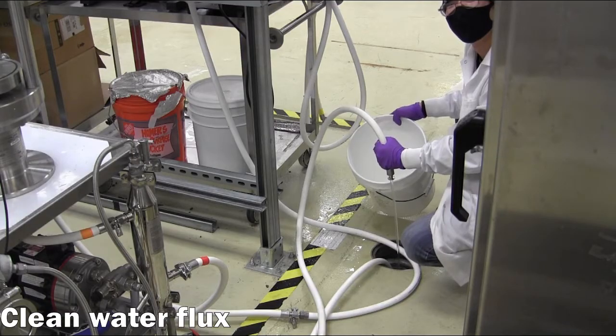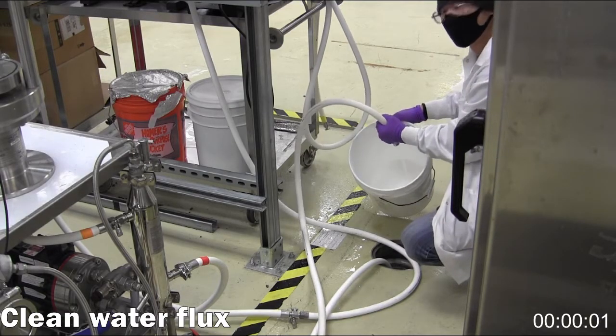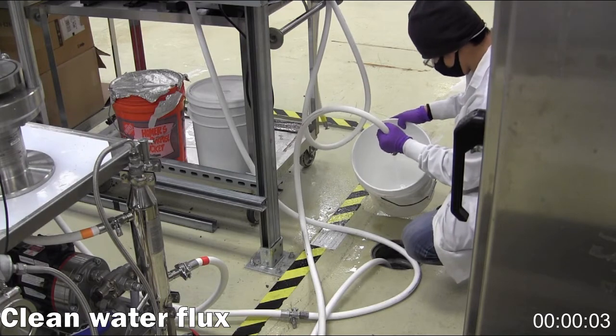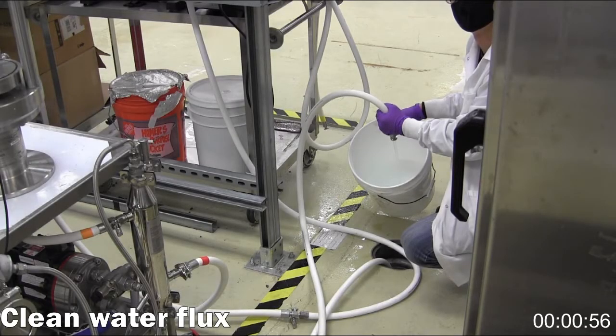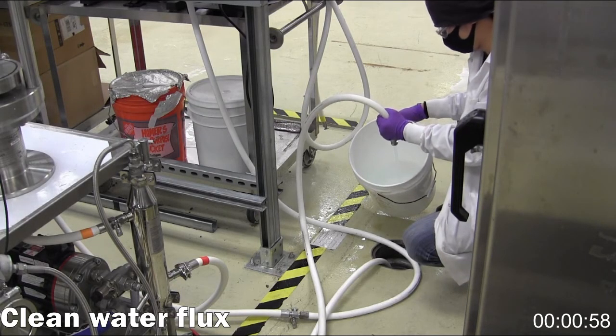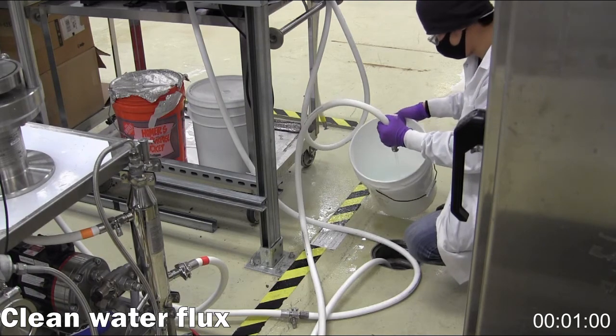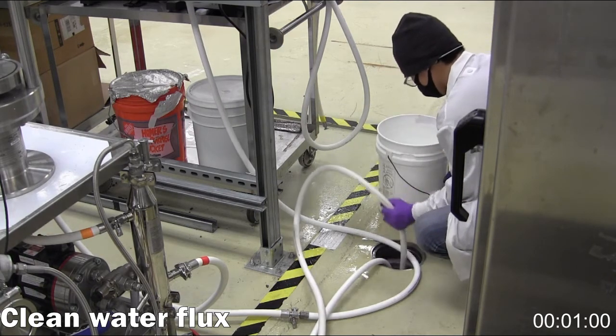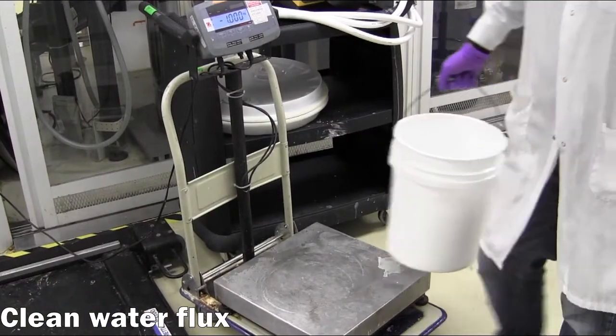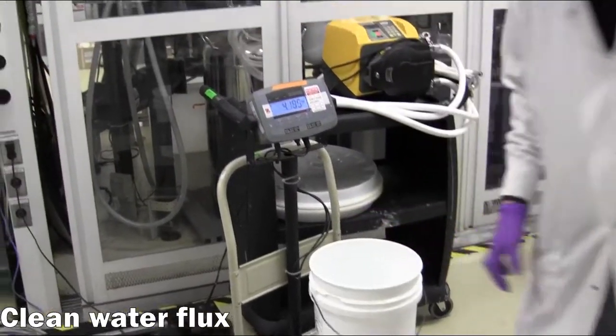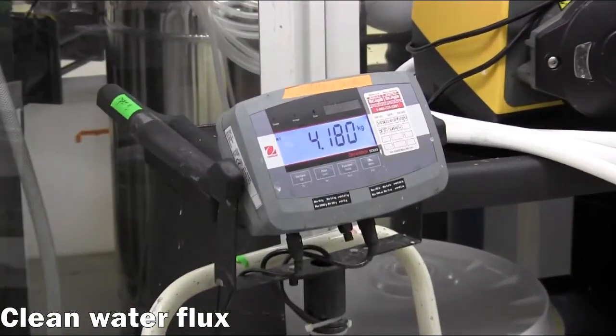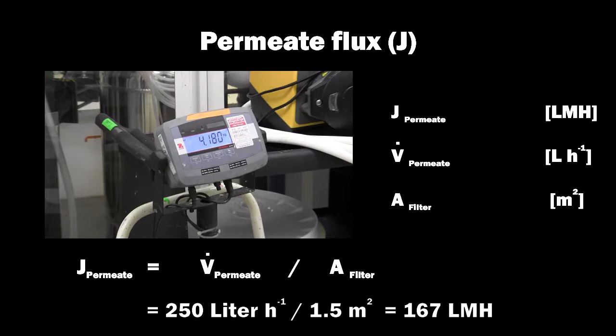The clean water flux is measured by collecting the permeate stream for a given time period, such as 1 minute. Then, the mass of water is used to calculate a flow rate and flux value using the membrane surface area. In this example, the clean water flux is 167 liters per square meter hour.